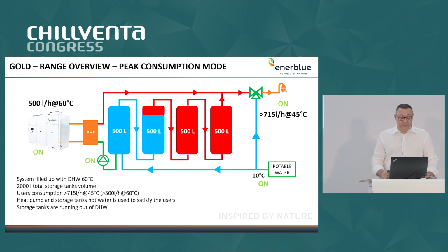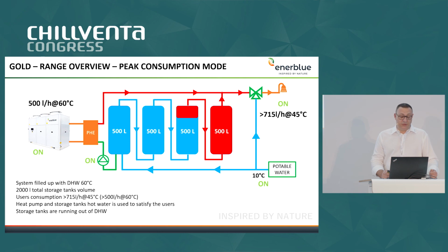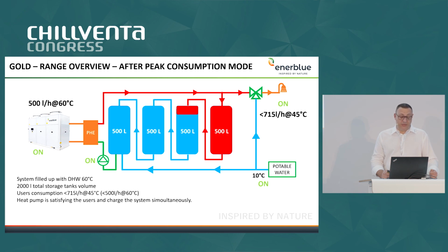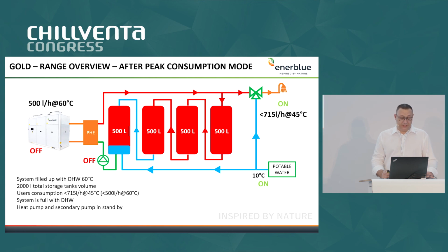When it is needed, the heat pump starts to work again. So when we are in a peak period, we can use at the same time hot water from the tank and also hot water from the heat pump in order to satisfy the system. And this could satisfy the peak. When the peak is over, we can still satisfy the users and fill up the tank at the same time. And when the system is completely full again, the unit will stop, waiting for the next peak.